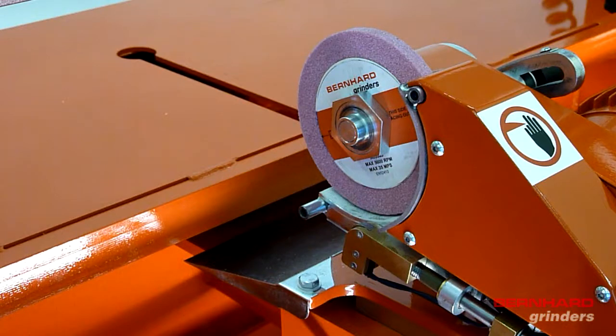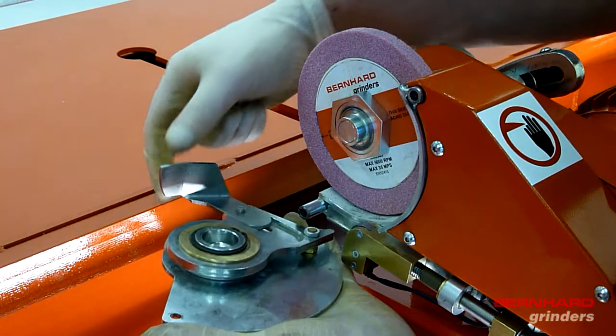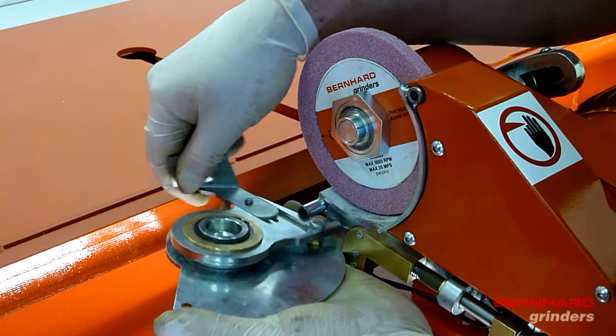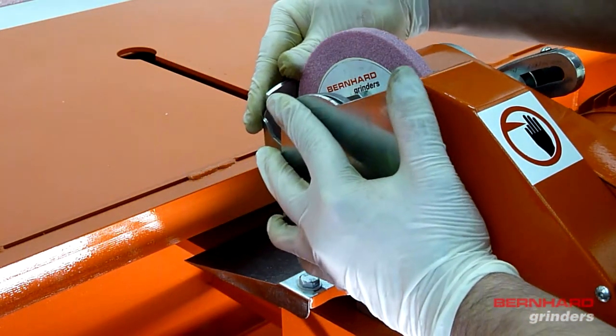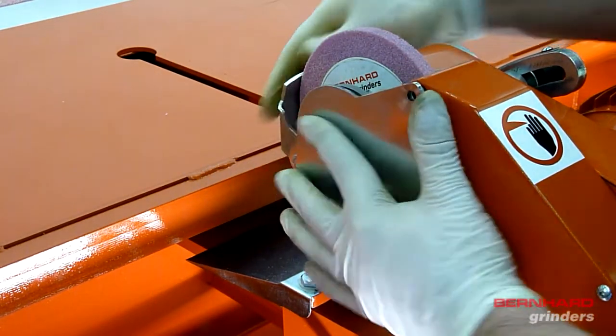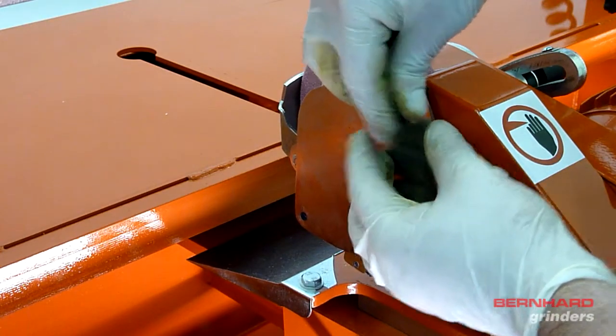When fitting the relief stone guard, make sure that the blade rest support follower is fitted in between the actuator head and the lower cover support post. The centre bearing is then located over the shoulder of the stone retaining nut. The guard is then secured using the 2 thumb screws.